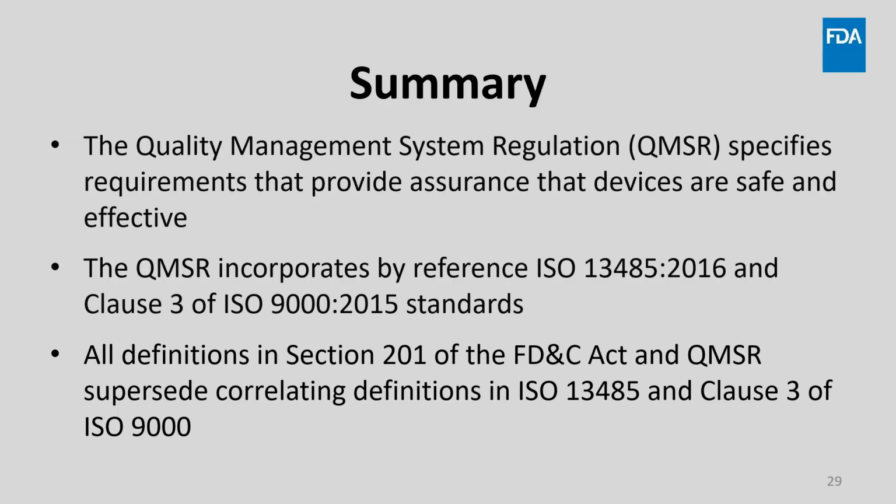In summary, the Quality Management System Regulation, QMSR, specifies requirements that provide assurance that devices are safe and effective. It incorporates by reference ISO 13485-2016 and Clause 3 of ISO 9000-2015 standards, and all definitions in Section 201 of the FD&C Act and in the QMSR supersede correlating definitions in ISO 13485 and Clause 3 of the ISO 9000 standards.